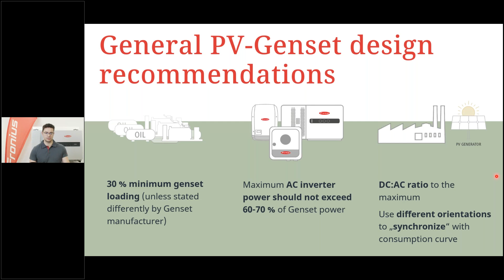Point number 3 is you can do a DC to AC ratio to the maximum, meaning every Fronius inverter has the possibility to oversize it. So on a 100 kilowatt inverter, you can put up 150 kilowatt peak on the roof in solar modules. This means you simply have more energy during the day. Also, you might want to think about different orientations to synchronize to your loading. For example, an east-west installation gives you more yield early and later in the day. This is also something you can think about when doing the first design.